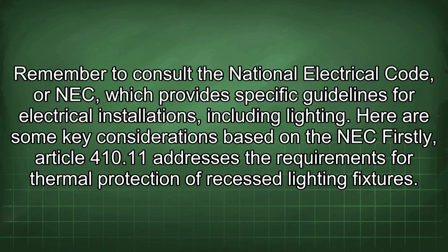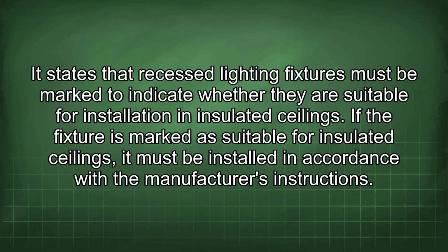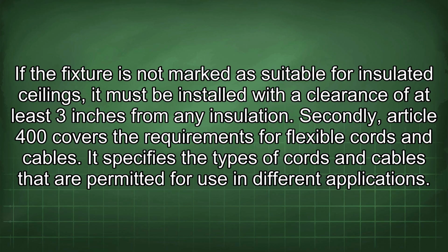Remember to consult the National Electrical Code, or NEC, which provides specific guidelines for electrical installations, including lighting. Here are some key considerations based on the NEC. Firstly, Article 410.11 addresses the requirements for thermal protection of recessed lighting fixtures. It states that recessed lighting fixtures must be marked to indicate whether they are suitable for installation in insulated ceilings. If the fixture is marked as suitable for insulated ceilings, it must be installed in accordance with the manufacturer's instructions. If the fixture is not marked as suitable for insulated ceilings, it must be installed with a clearance of at least 3 inches from any insulation.